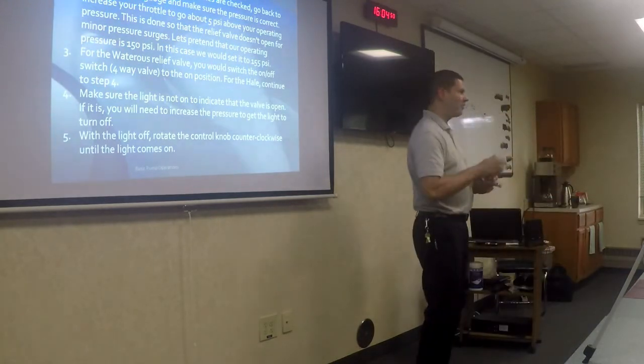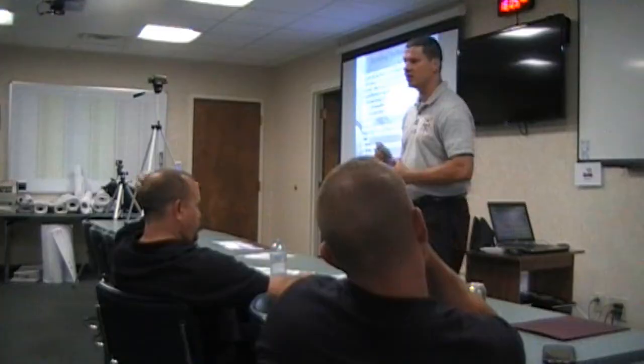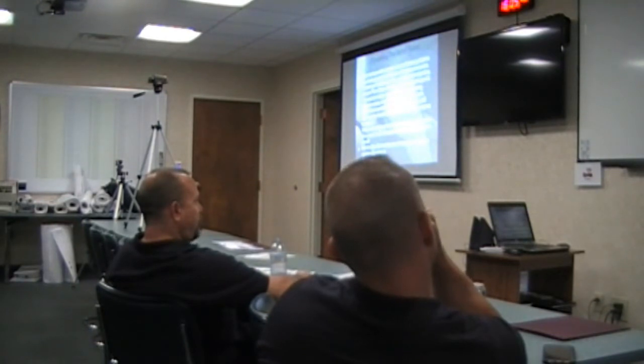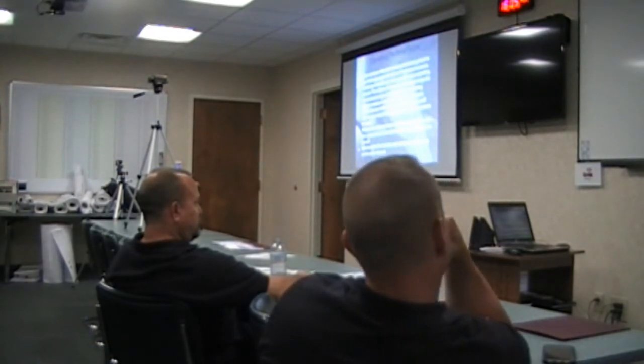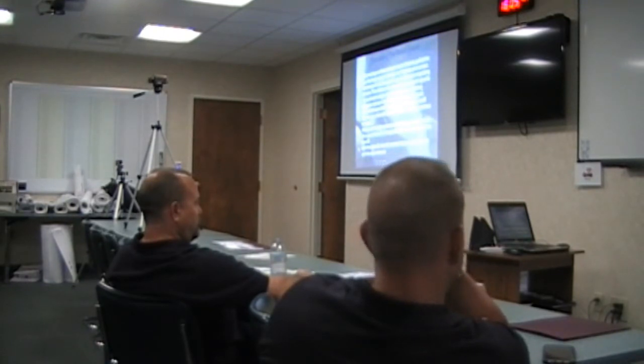What I'm telling you to do is throttle up to 155, okay, and that's when you should set the relief valve. So you throttle up to 155, the relief valve is closed. Then what? Increase it till it opens. You're gonna increase it till it opens, right? Drop it down till the light comes on. The light comes on, go back up, right? And then come back. So it's at 155, you throttle up, you turn the relief valve, drop it until the relief valve light comes on, go back up till it's closed, and then you should be good to go. Okay, again, easier to do than it is to explain.